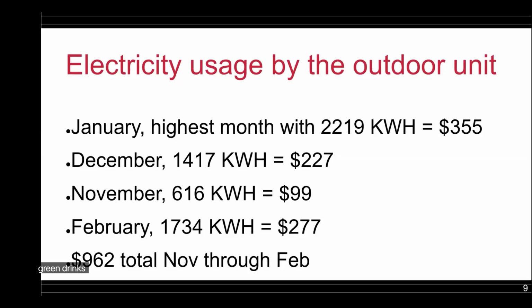You may be saying, Jeff, that's a huge amount of energy. I have a 10 kilowatt backup heat unit because, again, I don't have gas for backup. Most thermostats will switch to backup heat when you get 3 degrees below the set point. So if your set point is 70 degrees and the temperature drops to 67, the thermostat says that's bad and throws on whatever backup heat you have.